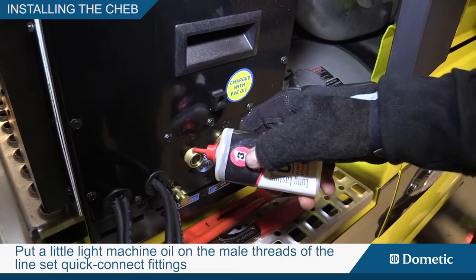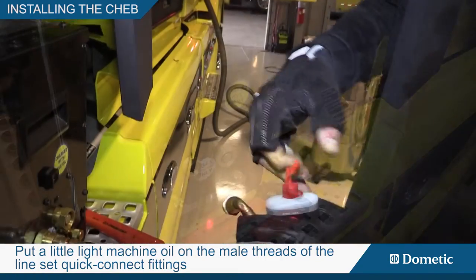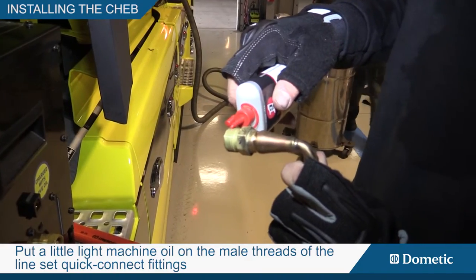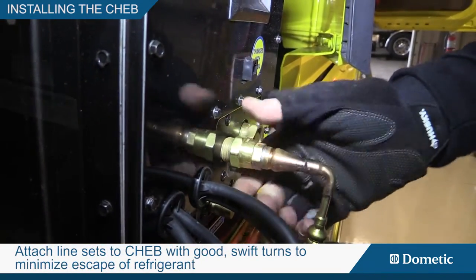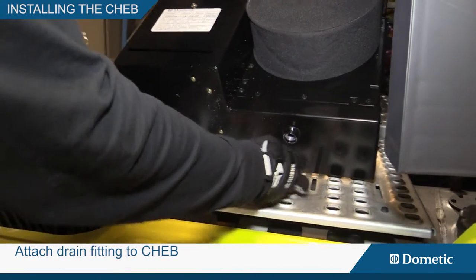Put a little light machine oil on the male threads of the line set quick connect fittings to help lubricate and make a good seal. Attach line sets to the CHEB with good swift turns to minimize escape of refrigerant. Attach the drain fitting to the CHEB.